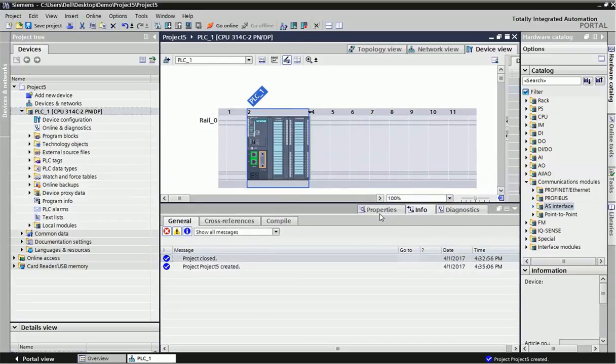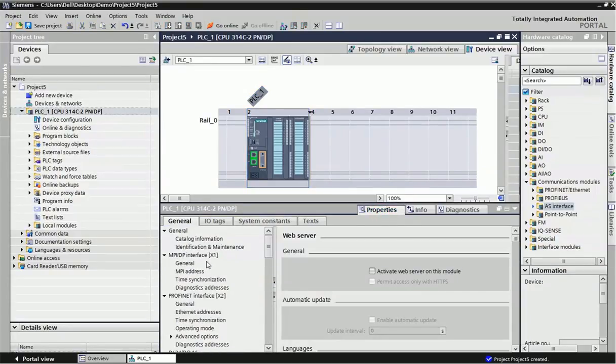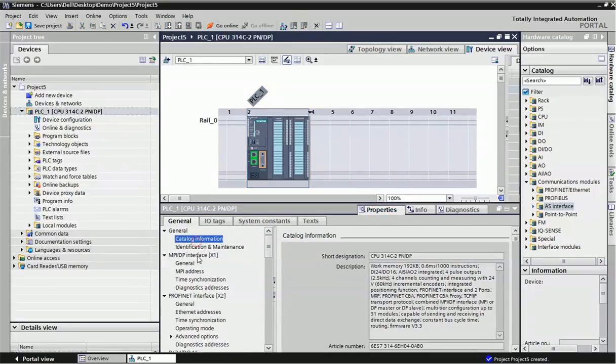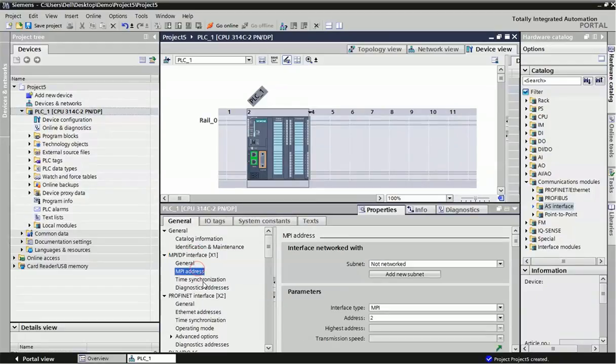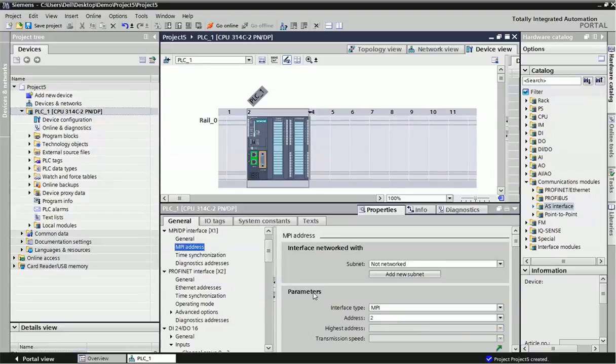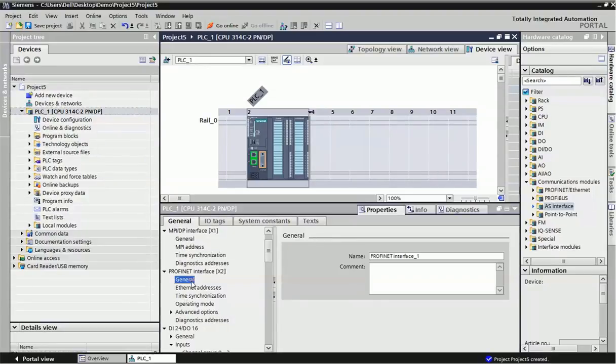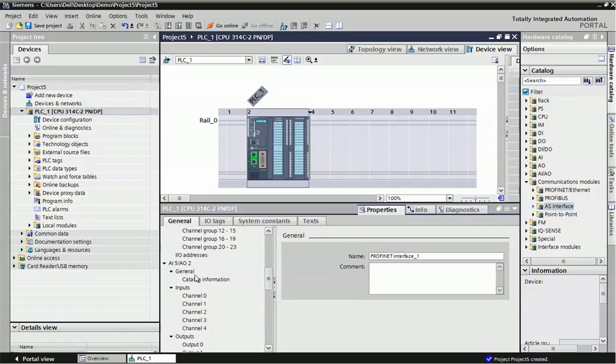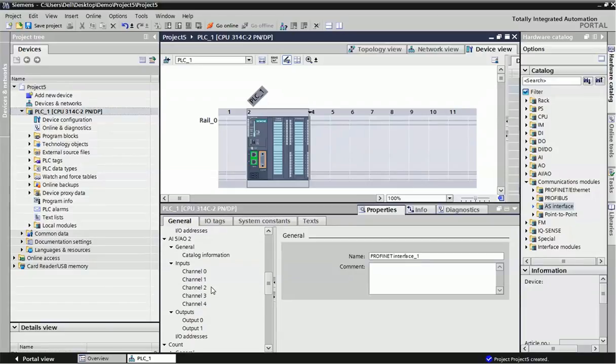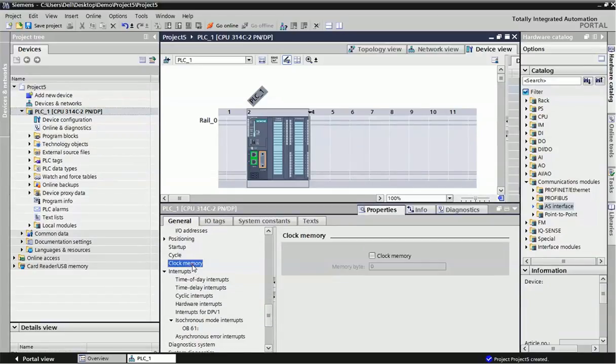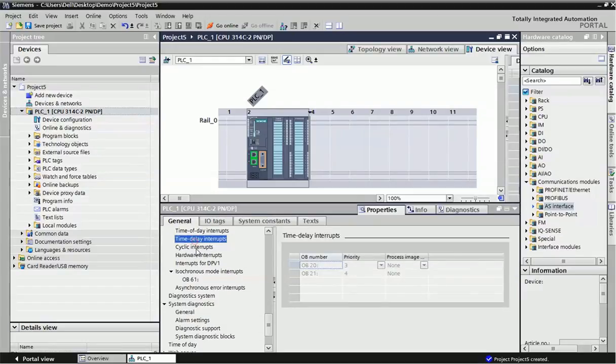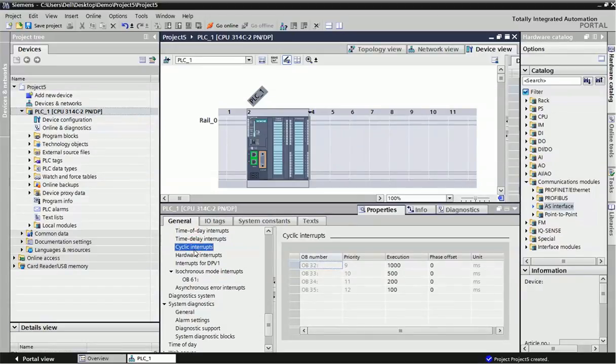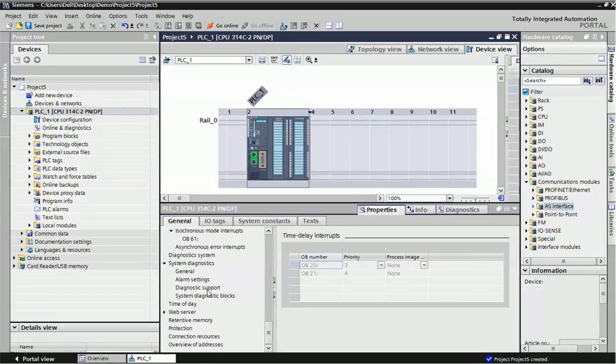Now in property, we will get detailed information about this PLC. What are the Ethernet address or MPI address that we can assign or we can change from this property window. And different types of analog and digital channels, clock memory, what are the hardware interrupts, time delay interrupts that we can assign from this property.